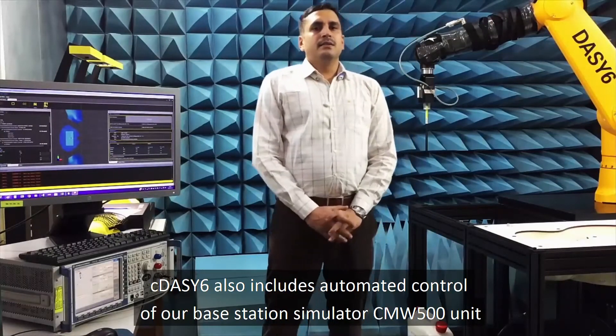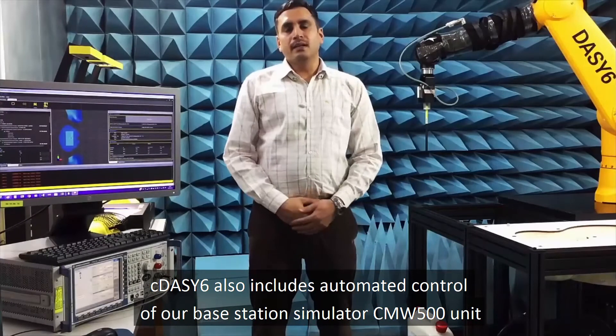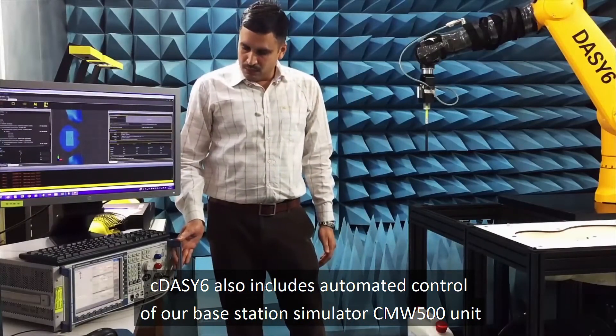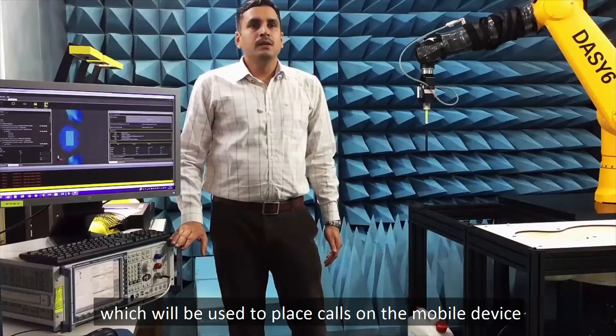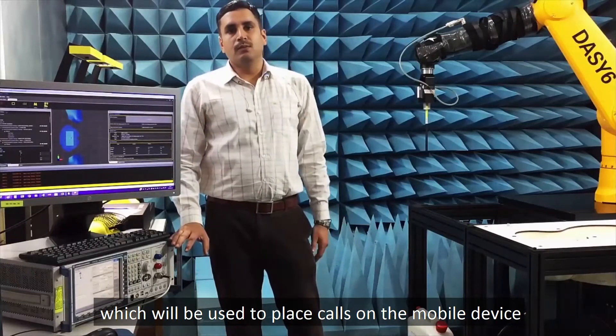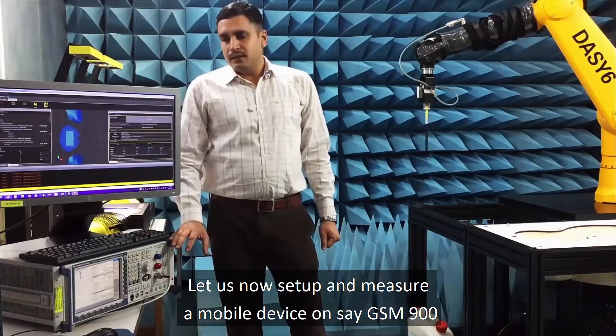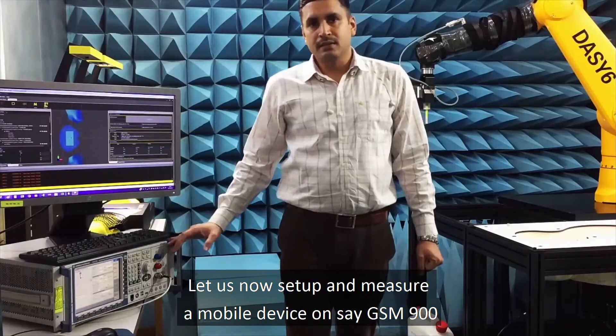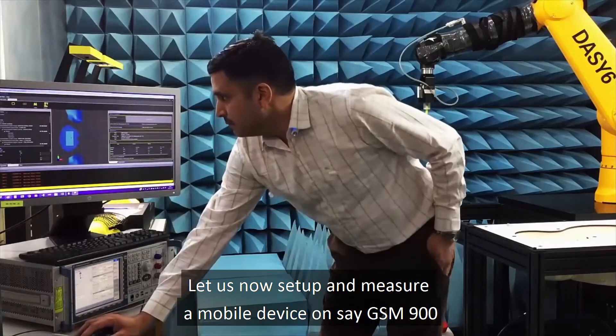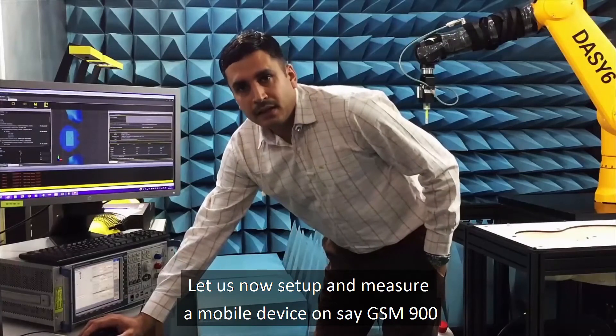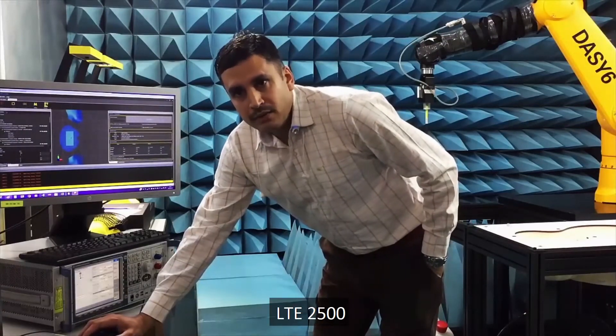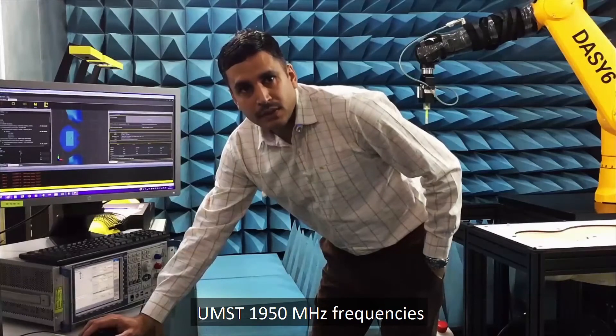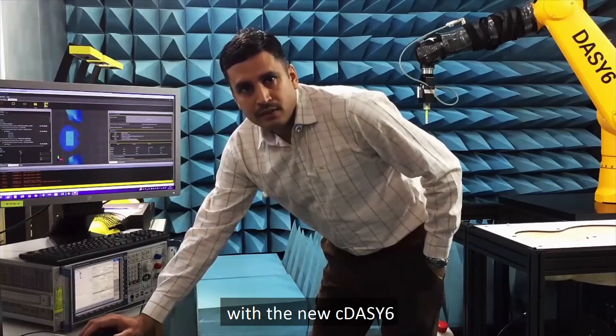cDASY6 also includes automated control of our base station simulator CMW500 unit, which will be used to place calls on the mobile device. Let us now set up and measure a mobile device on GSM900, LTE2500, and UMTS 1950 MHz frequencies with the new cDASY6.